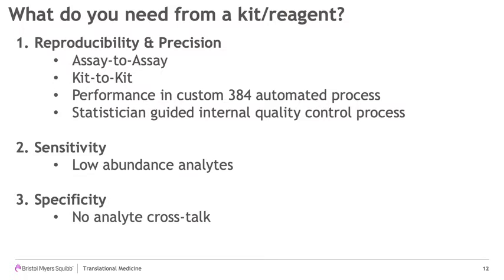This is something we will extensively test when new multiplexes come on the market that we want to add to our platform. Additionally, we work with an internal team of statisticians to ensure a robust QC process for all runs and reliably determine the lower and upper limits of detection and quantification. We have a database that keeps track of the key performance indicators for each assay run that will automatically flag if data falls outside of the pre-specified acceptance criteria.